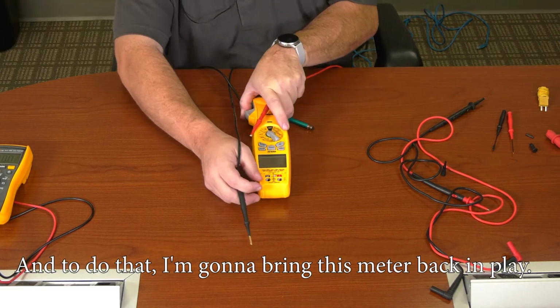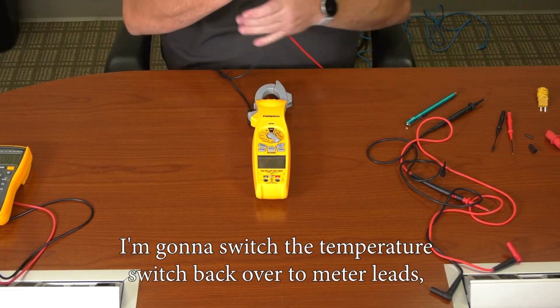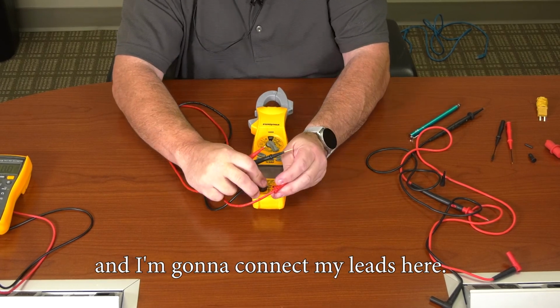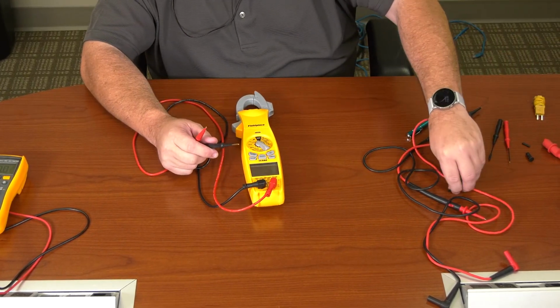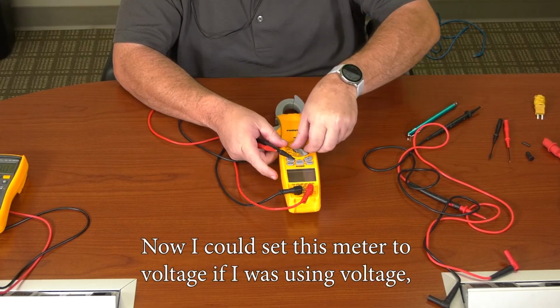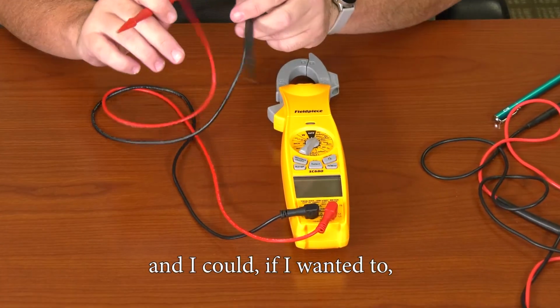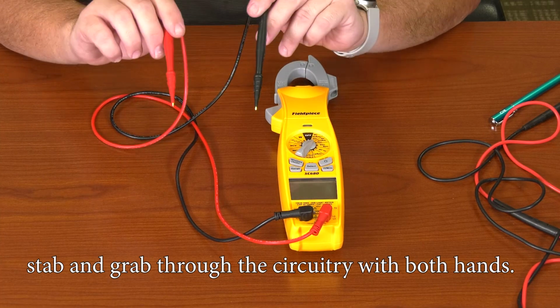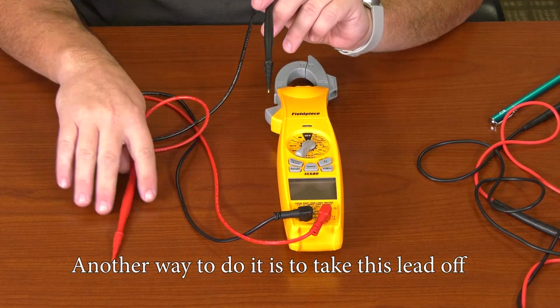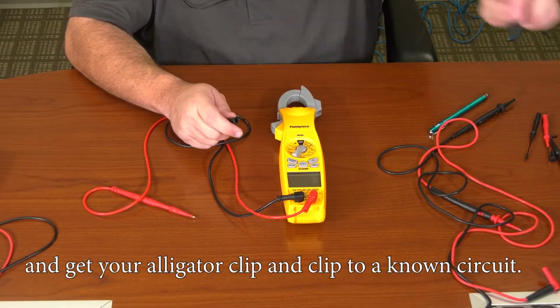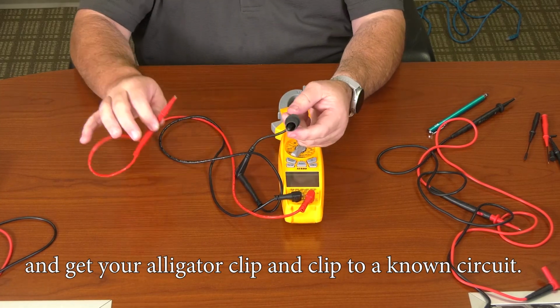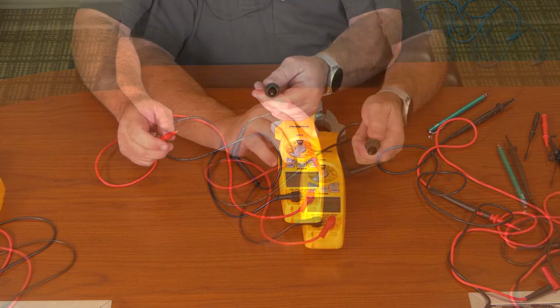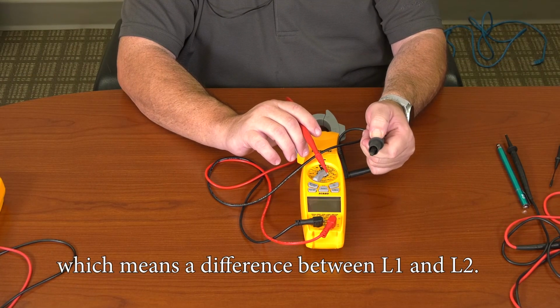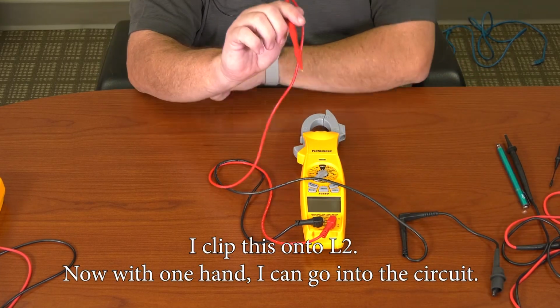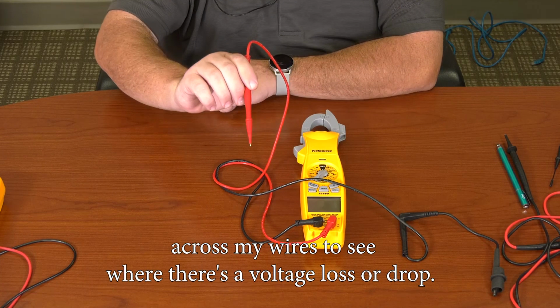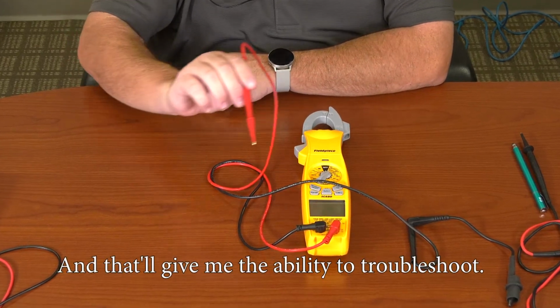And to do that, I'm going to bring this meter back in play. I'm going to switch the temperature switch back over to meter leads, and I'm going to connect my leads here. Now I could set this meter to voltage if I was using voltage, and I could, if I wanted to, stab and grab through the circuitry with both hands, but I run a risk. Another way to do it is to take this lead off and get your alligator clip and clip to a known circuit. Clip this on your L2 wire and leave it there. Because whenever I read voltage, I'm reading a potential difference, which means a difference between L1 and L2. Clip this onto L2. Now with one hand, I can go into the circuit across my wires to see where there's a voltage loss or drop. And that'll give me the ability to troubleshoot.